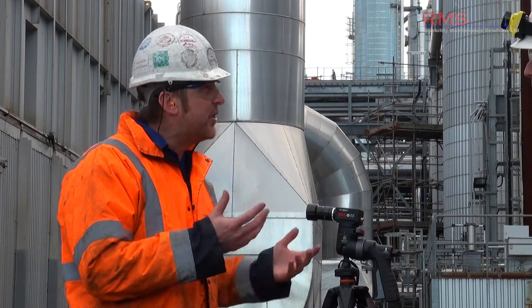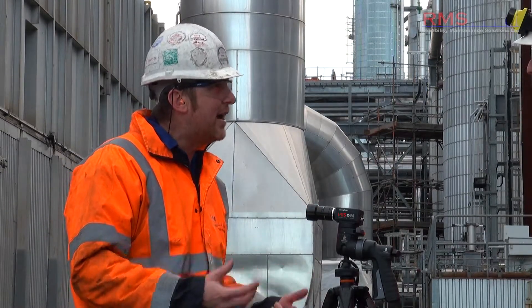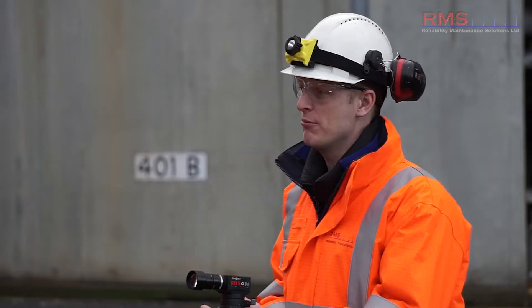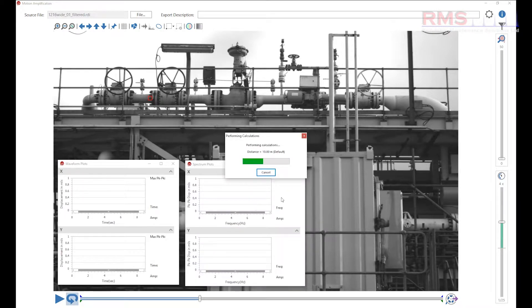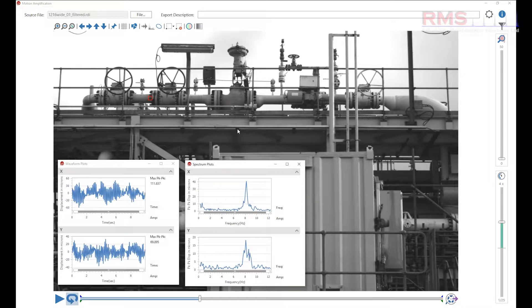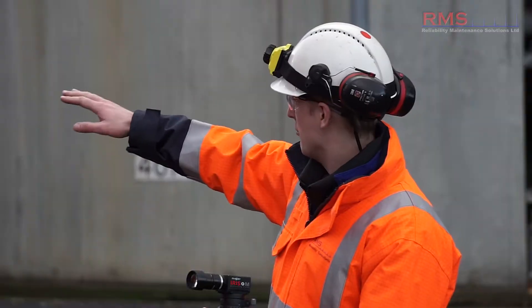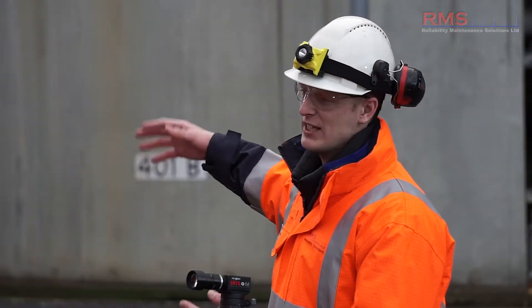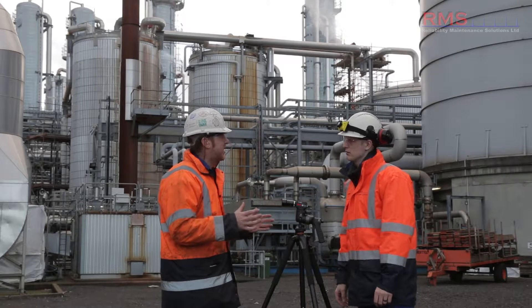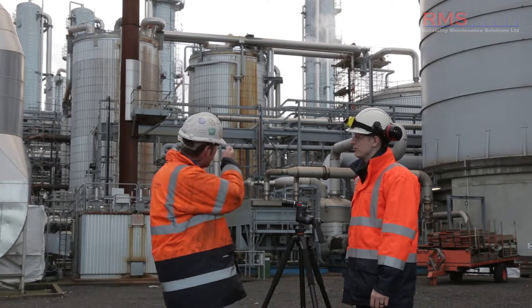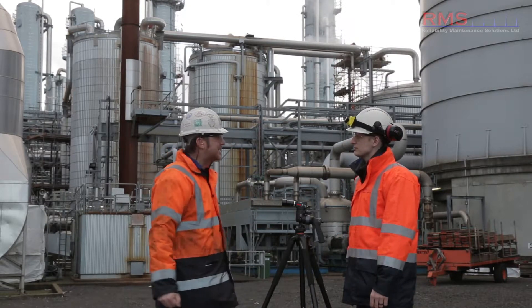We could literally turn the camera right now, get some shots, and just pick out measurement points along the pipework that we wanted. So we could measure deflection along the whole pipework — you can see there — we can take 10, 20, 30 readings. How accurate is it? Is it as accurate as going up there and putting an accelerometer on?